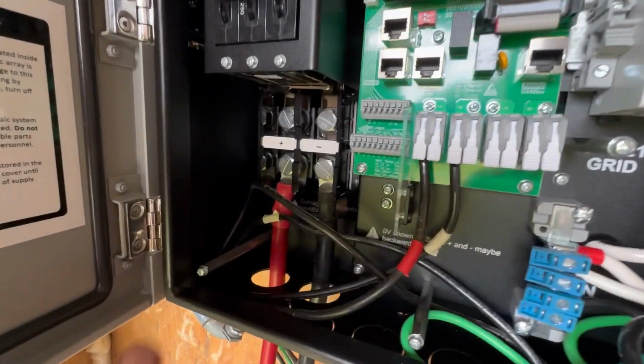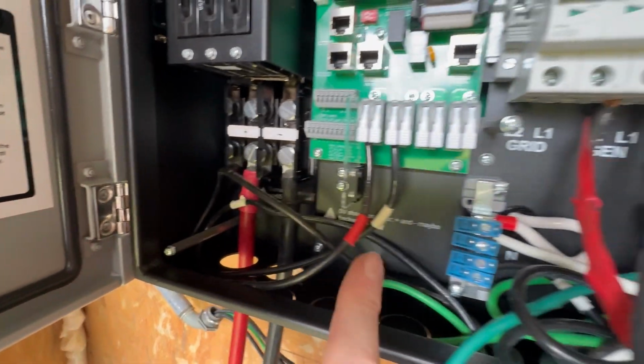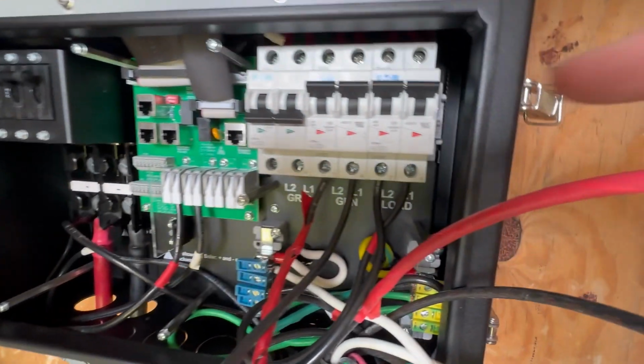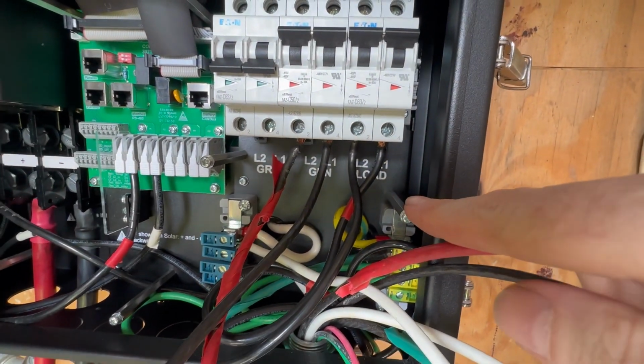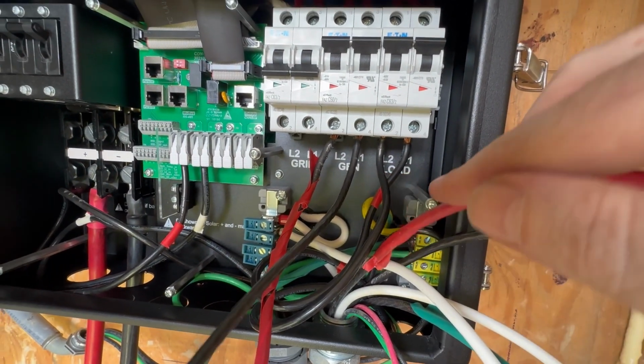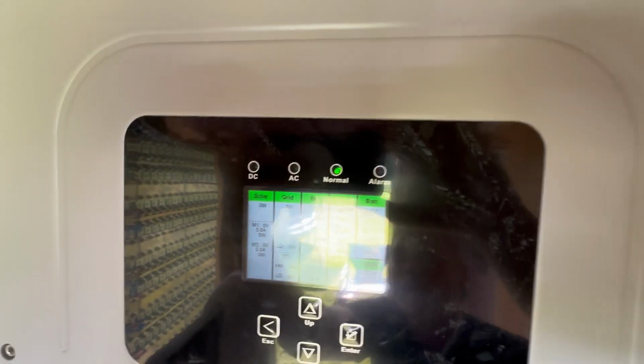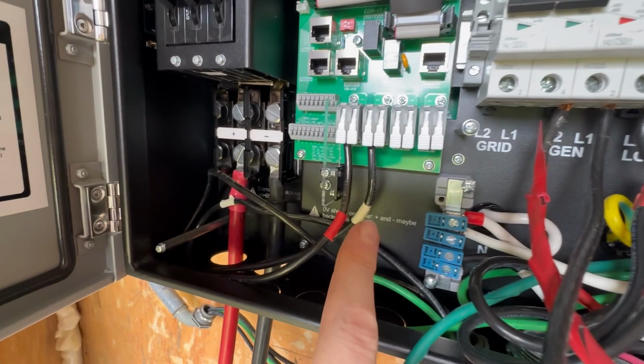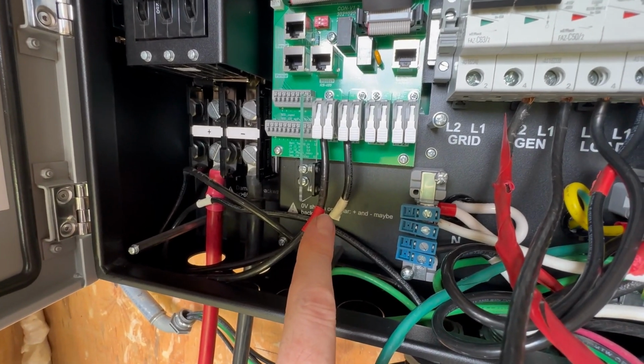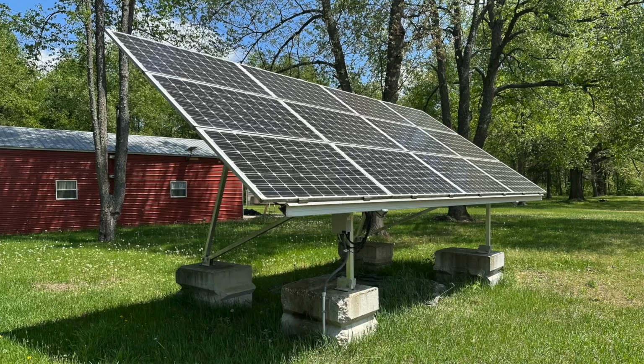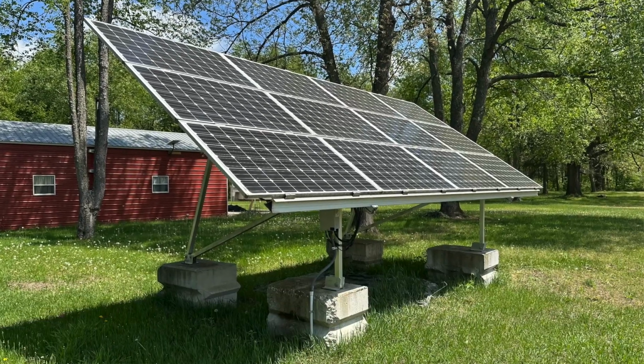Luckily the lugs on the battery terminals were already the right size, so I just put those cables in and tightened them up. The load section for the cabin's load panel reached, so I plugged those in, then plugged in the solar. There's only one string coming from the combiner box, so I only used one of the MPPT inputs, but that's fine since all 12 modules are in the same plane. It's a ground mount system, they don't get much shading, so having them all on one string is fine. I plugged that in, crossed my fingers, turned everything on, and the solar was pumping out power.